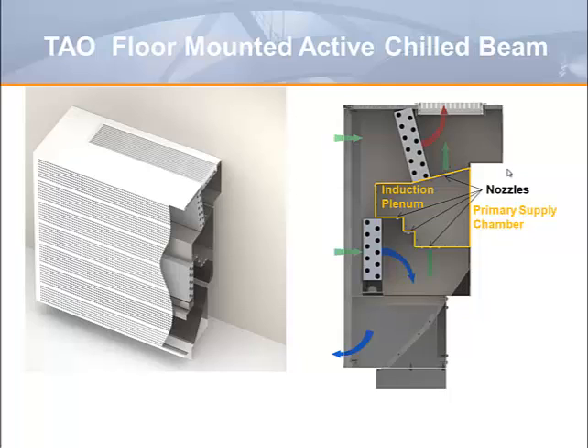This cross-sectional view shows where the dedicated outdoor air system inlet feeds a series of nozzles in an upper chamber for heat and a lower chamber for cooling. The nozzles induce room air through a perforated front panel, which can be heated as it passes through the upper coil or cooled as it passes through the lower coil. The conditioned air is distributed through an outlet on the top of the unit for heating loss on the glass and back into the lower perforated face to handle the sensible heat gains in the space.